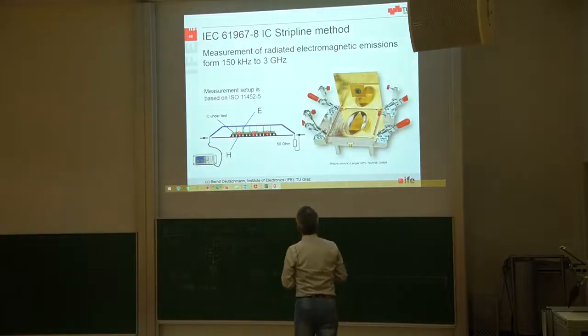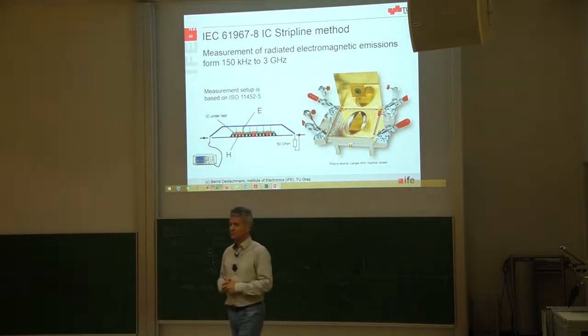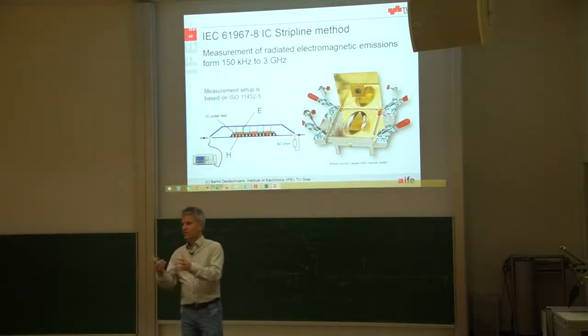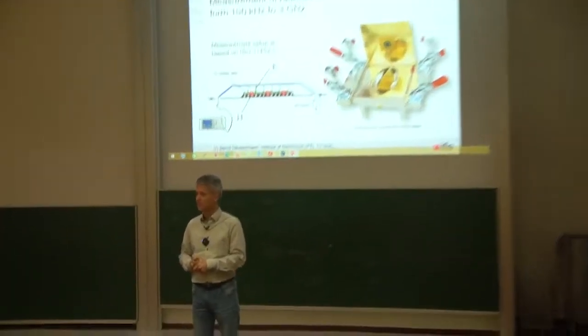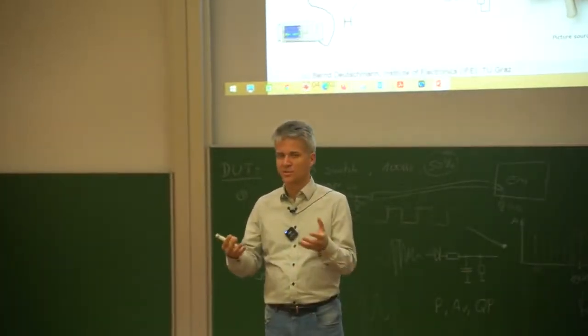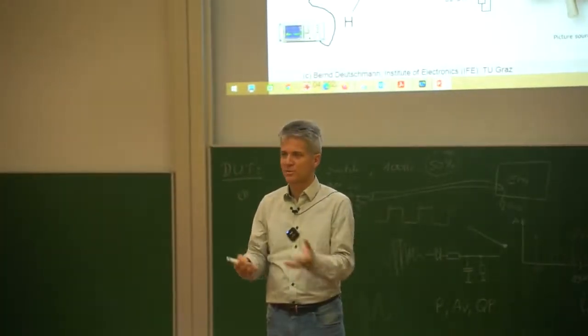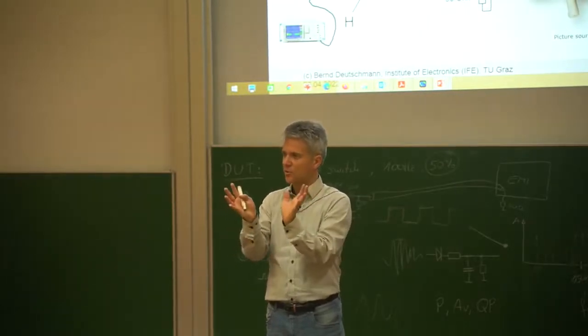The latest measurement technique available is defined in IEC 61967-8, called the IC stripline method. It operates on exactly the same principle as the TEM cell and GTEM cell. Imagine a TEM cell made smaller and smaller, and you will most probably end up with the IC stripline.